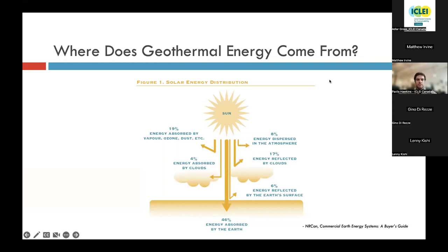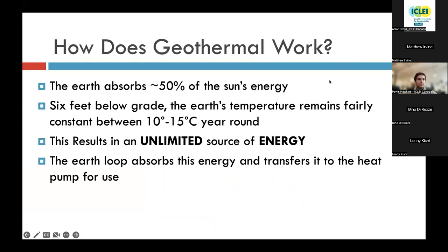But as I said, the Earth does absorb almost 50% of the sun's energy every day. And 6 feet below grade, the Earth's temperature remains fairly constant between 10 and 15 degrees Celsius year-round anywhere in Canada. This constant 10 to 15 degree temperature results in an unlimited source of energy. And the earth loop absorbs this energy and transfers it to the heat pump for use in the house.